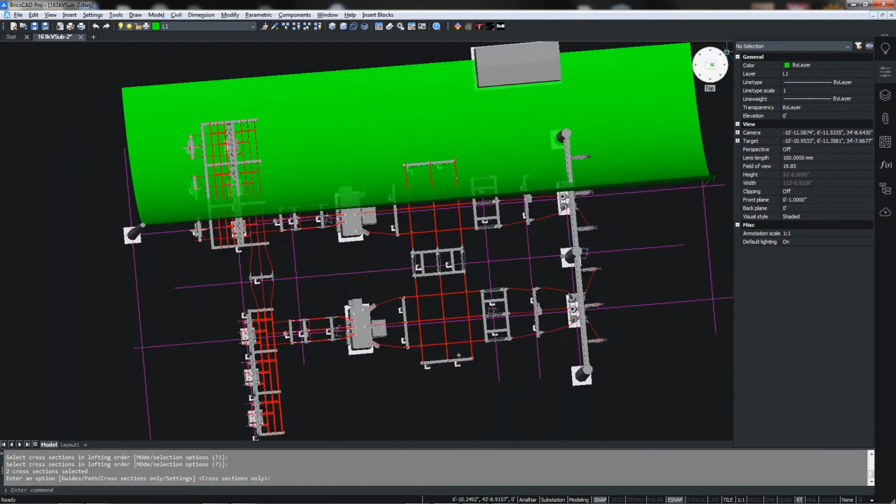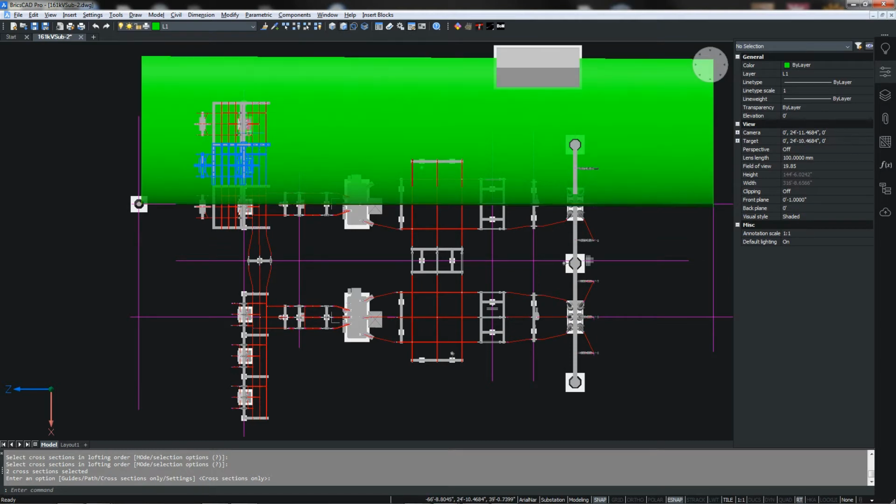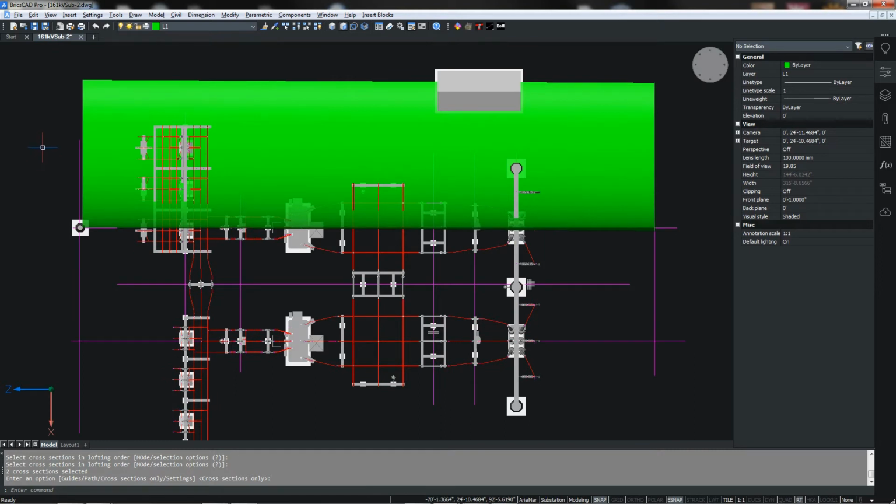So looking at that from overhead, we're going to take a similar approach to what we did in our fixed angle, and we're going to rotate this static. And let me just say, we can't go all the way to where we cover all of this bus. If we go too far, then the distance between our static pole here and here will exceed the radius of our sphere, and the sphere will drop to the ground and will not be above our structure.